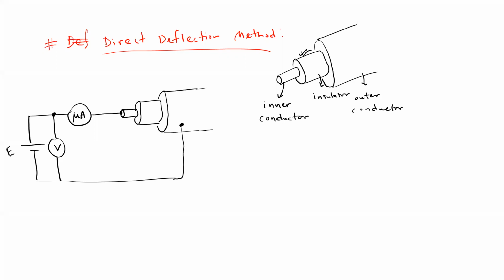For other cases, connecting the voltmeter before or after the ammeter doesn't have as significant an effect as it does here. Since the current is very low in magnitude, a very high voltage has to be supplied so that some current can flow through the insulating material. The voltage can range from 500 volts to 1000 volts, up to maybe 5000 volts even. So measuring this high resistance requires operating at very high voltage as well.